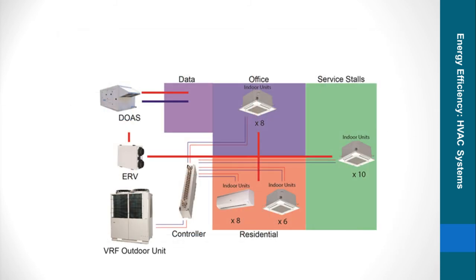In the final system layout, the data server room is supplied by the DOAS with 100% outdoor air, significantly reducing the cooling load. The return air from the data server room is used to preheat the outdoor air for the remainder of the building through the energy recovery ventilator. The remainder of the heating and cooling loads are handled by the VRF system.